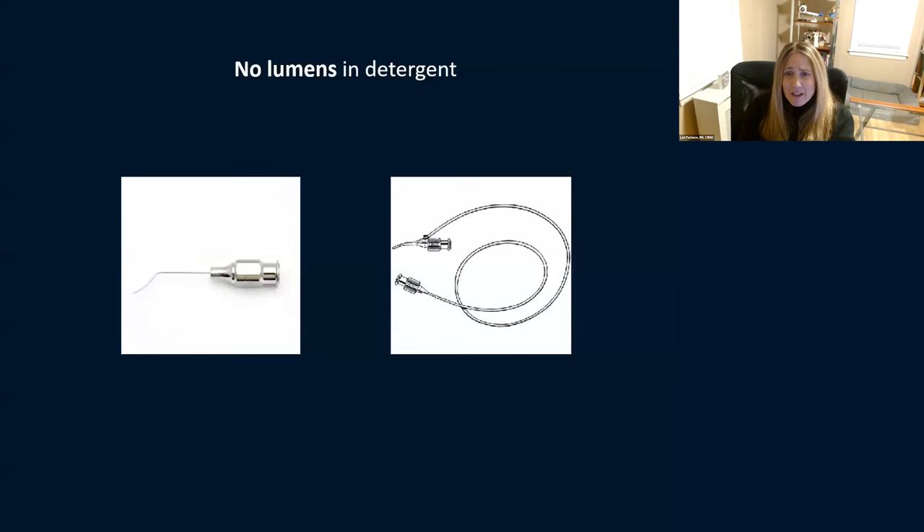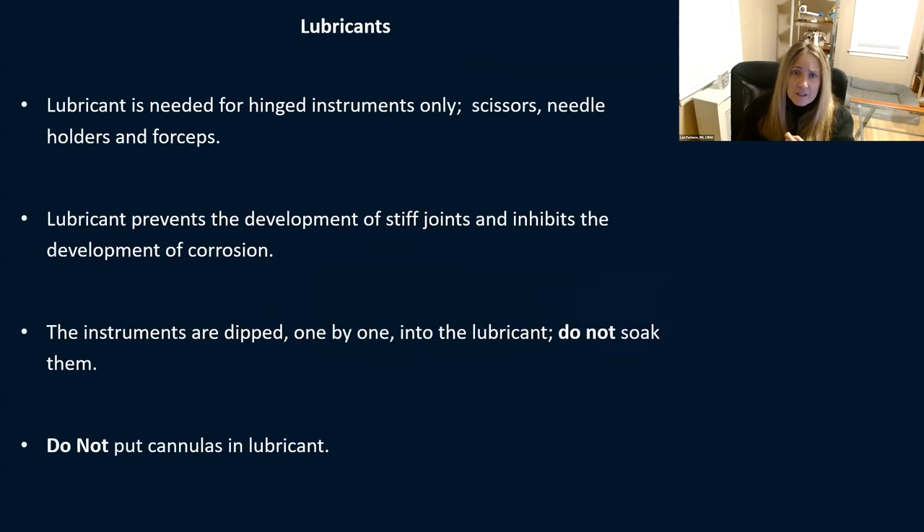No lumens in detergent — it's a big risk for TASS. Still want to be flushing your instruments and using compressed air, but try not to put detergent through lumens. You can use lubricants for hinged instruments — this helps them open and close properly. There's nothing worse than handing scissors to a surgeon that don't open. Lubricants are for scissors, needle holders, and forceps, helping prevent stiff joints and inhibit corrosion. Usually instruments are dipped one by one in the lubricant, not soaked. Don't use lubricant in cannulas.